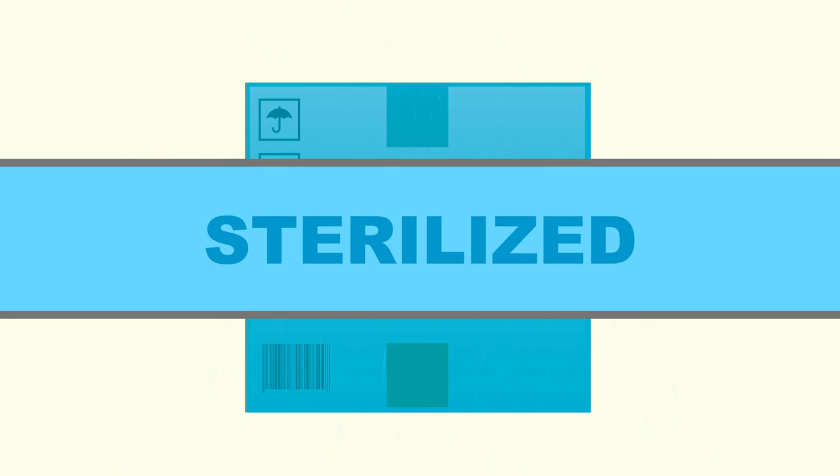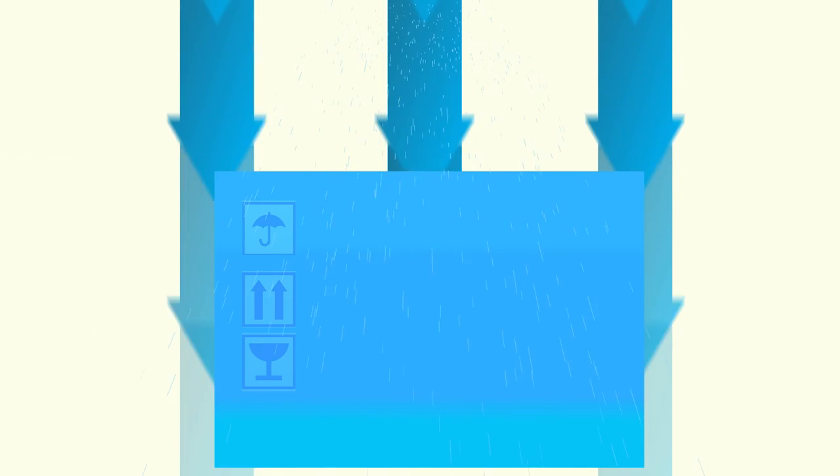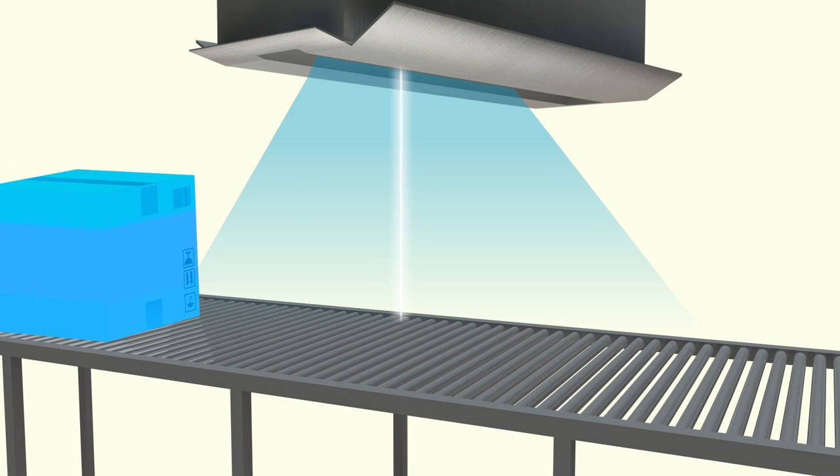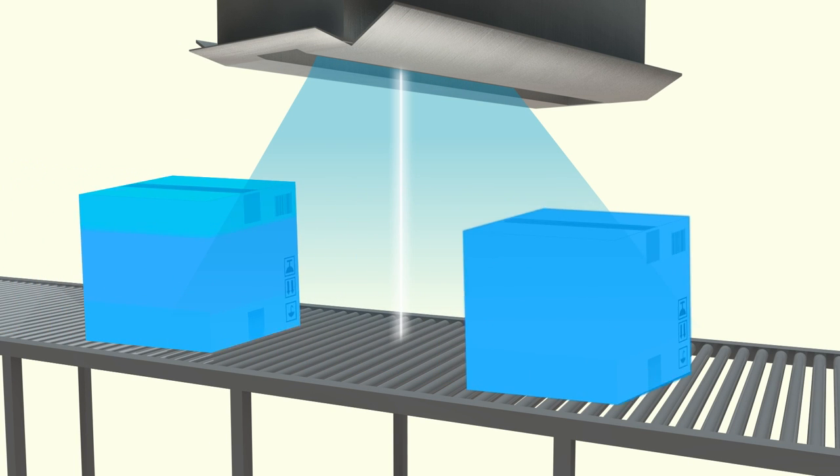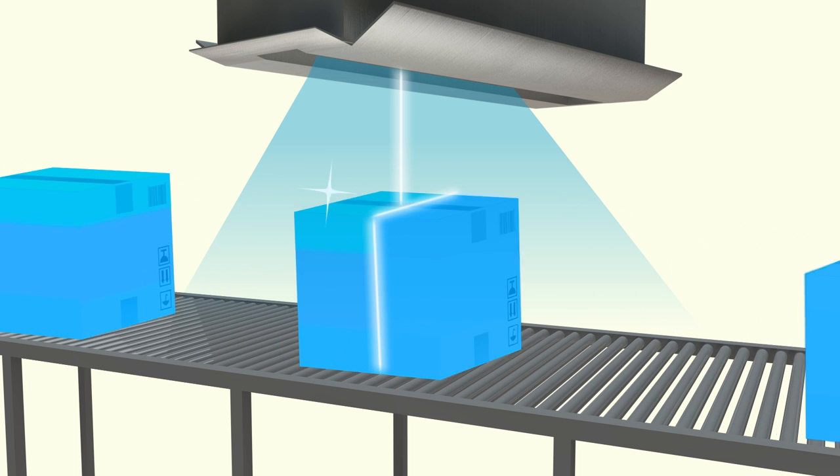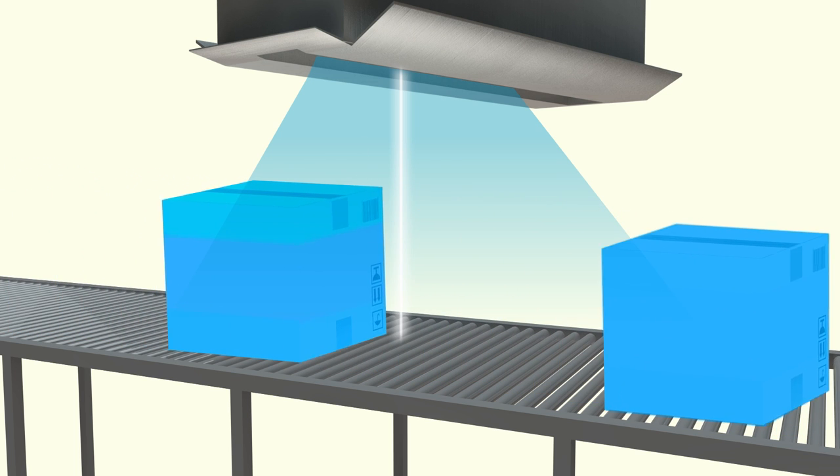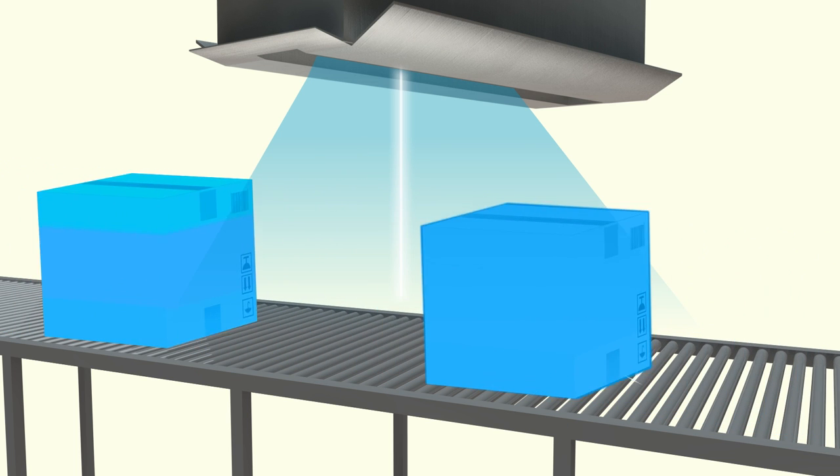As the electrons penetrate the products, the radiation dose diminishes, so less radiation leaves the box than entered. Medical devices are usually turned over and irradiated from the opposite side in order to get a relatively uniform dose.